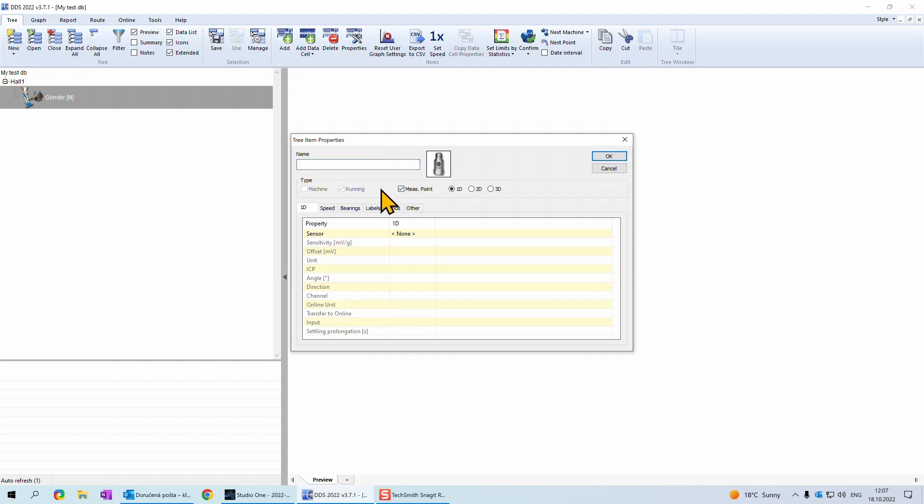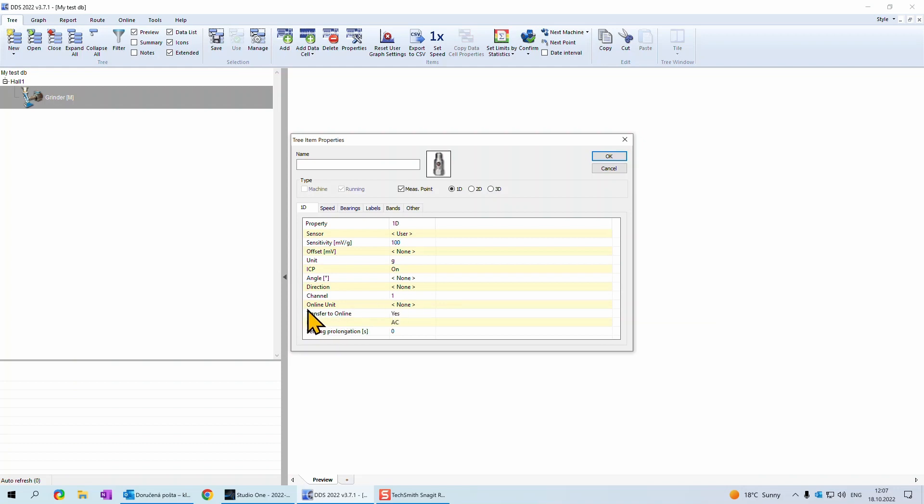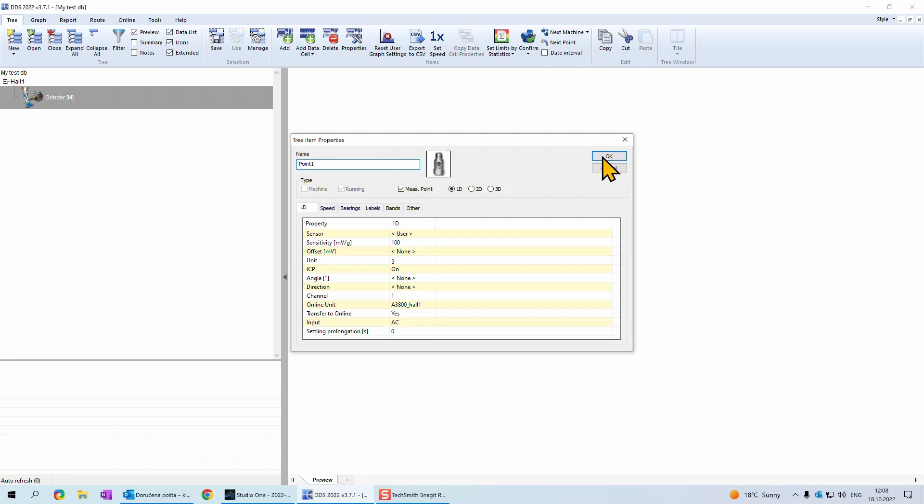Type needs to be measurement point. Firstly, we need to add sensor here and set its parameters. The most important is to set sensitivity, unit and ICP. We need to set up also channel where sensor is connected to online unit. Let's choose channel 1. Online unit needs to be chosen here. Choose the one we added, name this point and confirm this window with OK button.